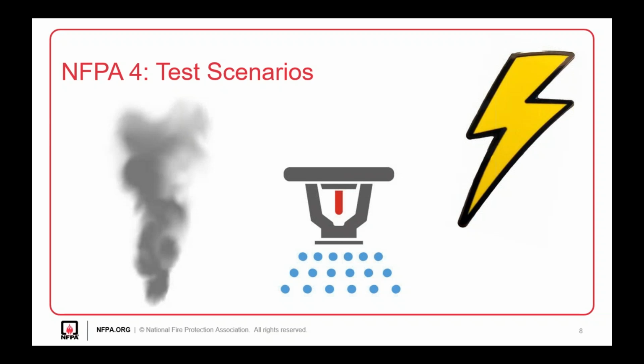That's why those three scenarios are set in place. So again, it's not a prescriptive standard that tells you which tests are required based on the type of occupancy or the systems in your building. It's really up to the integrated testing agent, the owner, and the authority having jurisdiction to develop the test scenario.